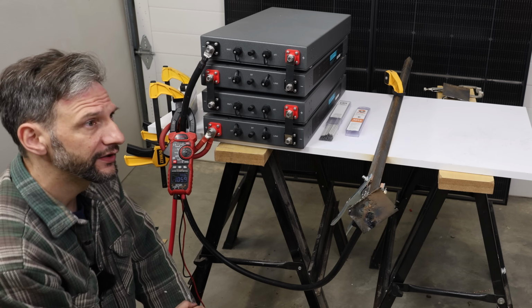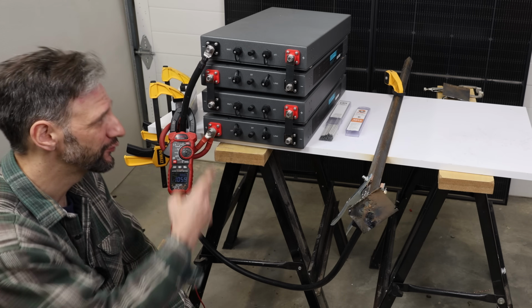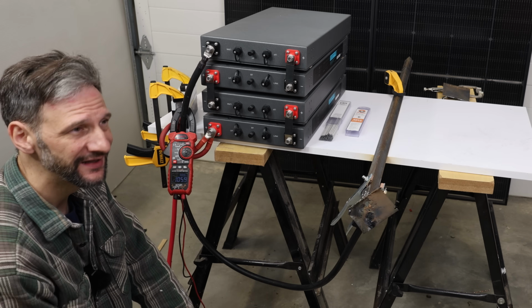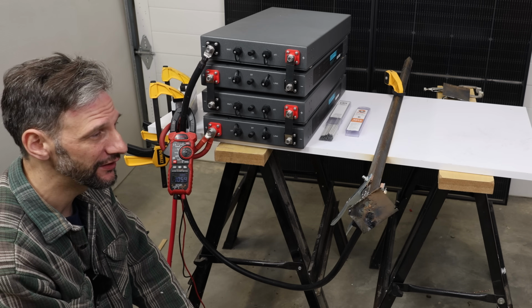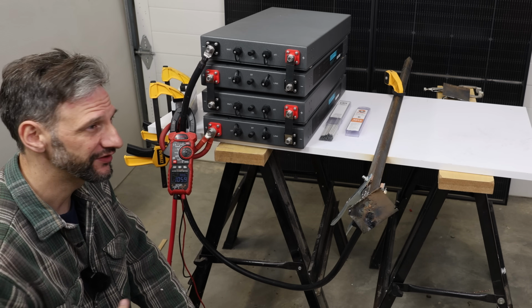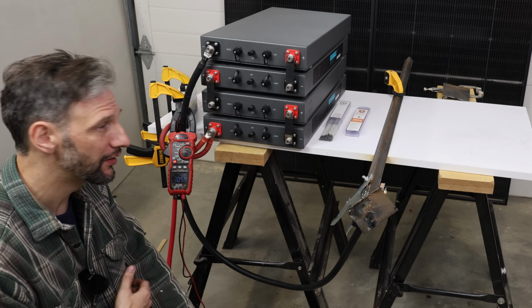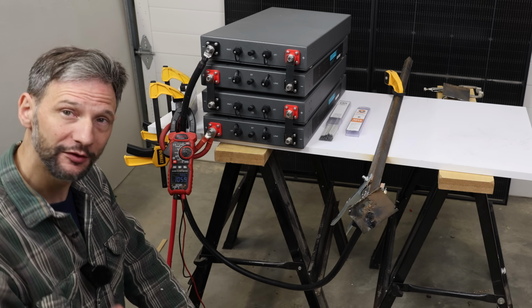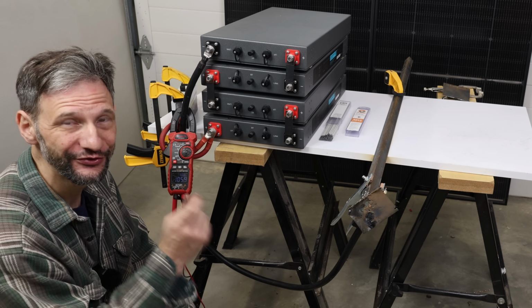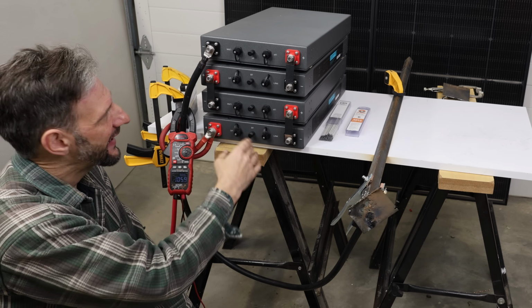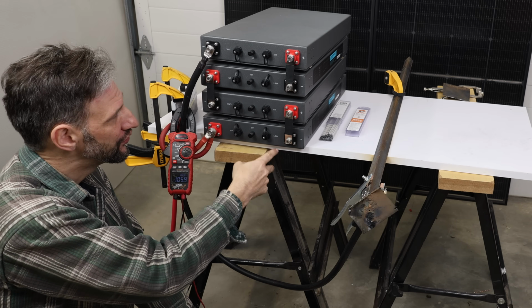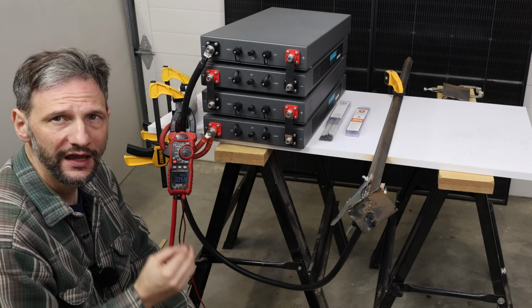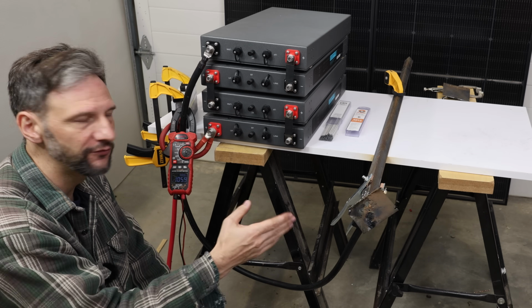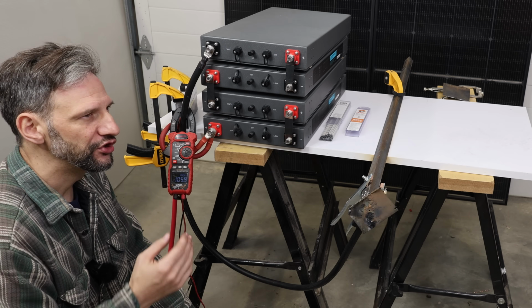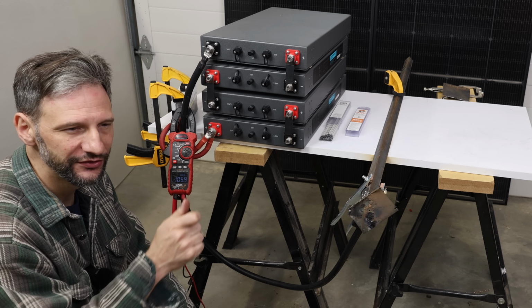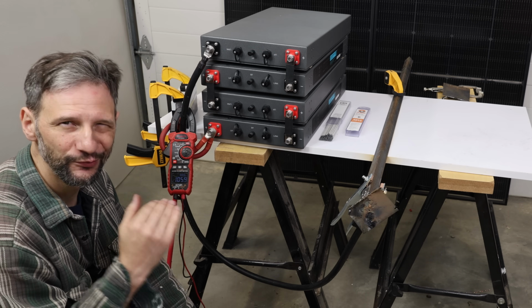So what have we learned here? The 24 volt configuration with 2 batteries in parallel is the closest you're going to get to being able to weld. The 12 volt configuration with 800 plus amps available will melt rod no problem, but it's just not enough voltage to create an arc. I think if we had 8 of these batteries, we could put 2P4S and probably be able to do 50 volt welding. But even then, you just can't dial in the precise voltage and current you want to work with, so it makes it really hard to weld.